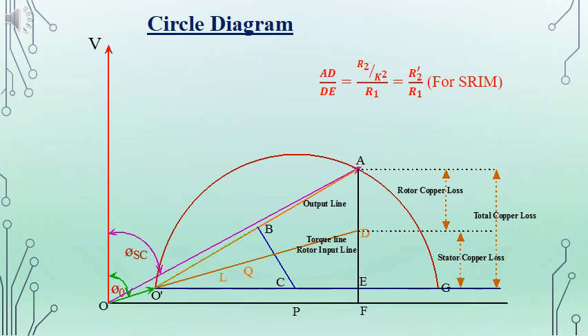In order to find point D, we divide the line AE. For a slip ring induction motor, the division is AD divided by DE equal to R2/k² divided by R1, which equals R2' divided by R1. For a squirrel cage motor, we find the length DE corresponding to stator copper loss, which can be obtained by measuring the stator resistance.